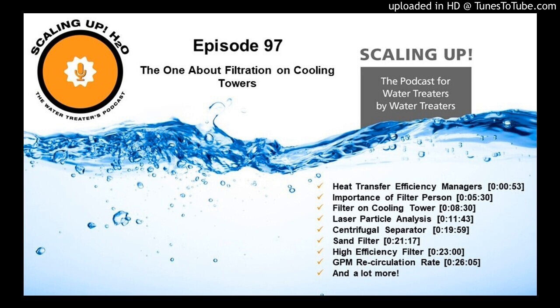And so when a filter is ordered, the water treater and the customer need to say to the filter guy, this has to be clean water backwashing. Sometimes you take water from the filtered water and put it into a tank that will be enough to cover one backwash, and you keep that tank leveled up with water from the filter. But you absolutely can't use tower water for backwash. It's a bad plan. Do you have to worry about biological fouling when you store water like that?